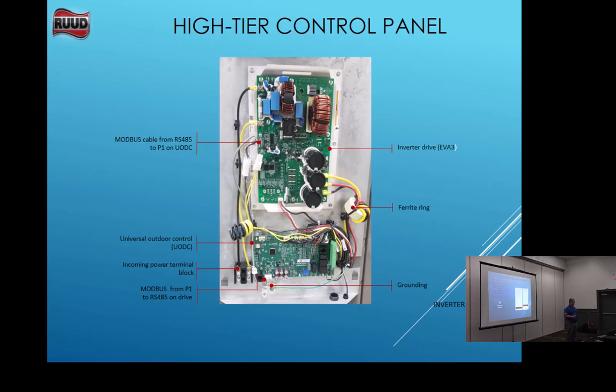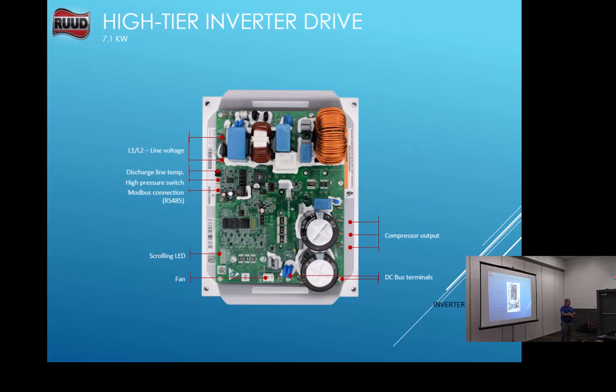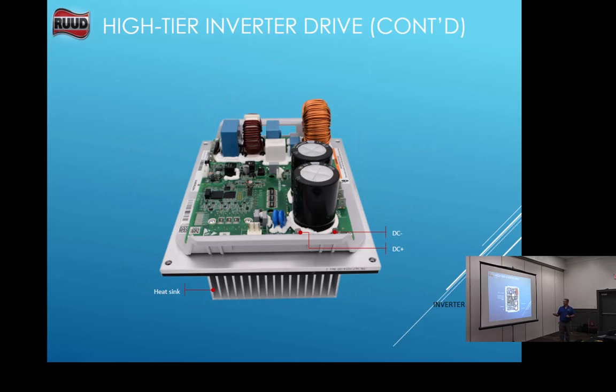This is our high-tier control board. It's made by Emerson. Same people that made the boards for our 17s and 20s. Okay. Basically the same board. Power in, power out, drive is good. And one other thing that you can check on this one is it's got DC bus terminals right here that you can check your DC output bus on that board. So if you have 240 volts, whatever voltage you have going in AC, it's 1.4 times the amount of DC voltage coming out. So if we have 240 going in up here, DC voltage should be around 330, 340 volts DC. And you'll know that you have the proper DC voltage coming out. All right?